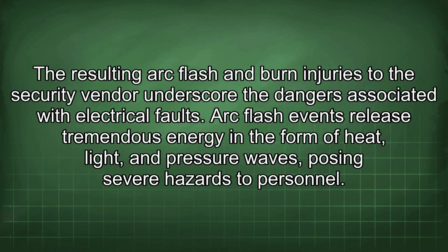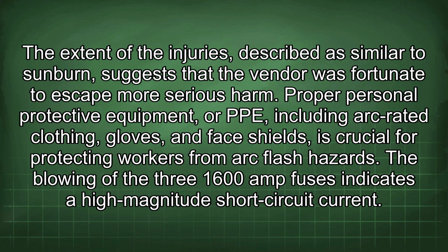The resulting arc flash and burn injuries to the security vendor underscore the dangers associated with electrical faults. Arc flash events release tremendous energy in the form of heat, light, and pressure waves, posing severe hazards to personnel. The extent of the injuries, described as similar to sunburn, suggests that the vendor was fortunate to escape more serious harm. Proper personal protective equipment, or PPE, including arc-rated clothing, gloves, and face shields, is crucial for protecting workers from arc flash hazards. The blowing of the three 1600 amp fuses indicates a high-magnitude short-circuit current.